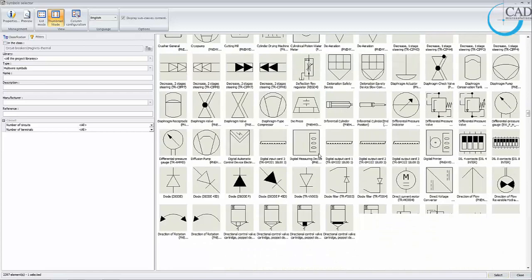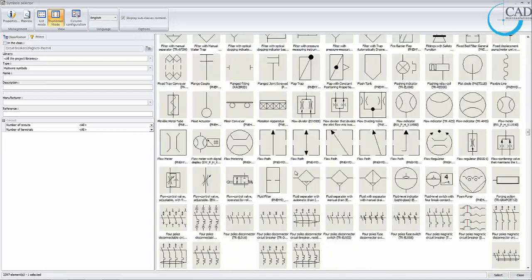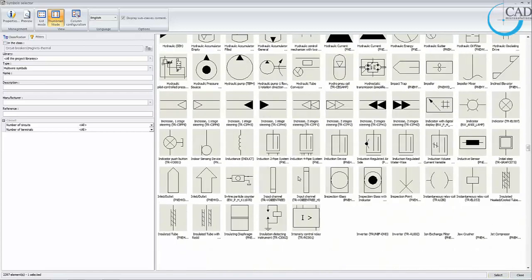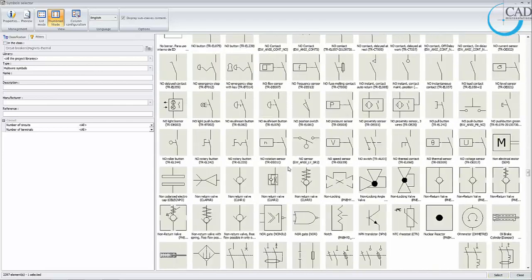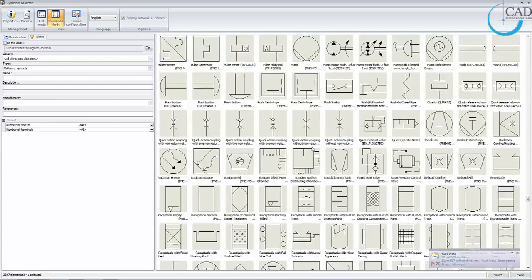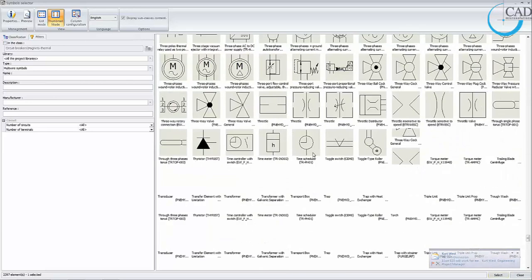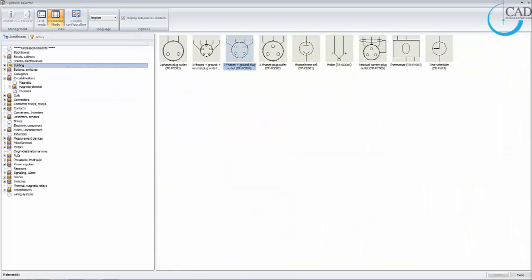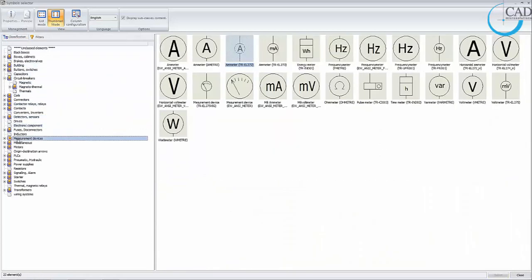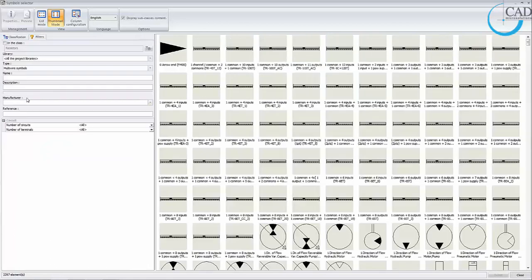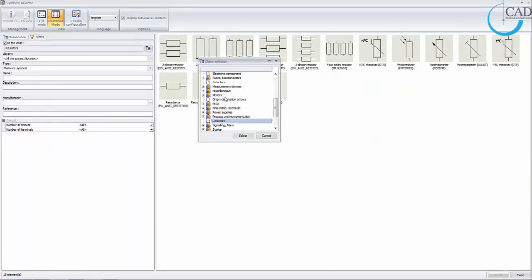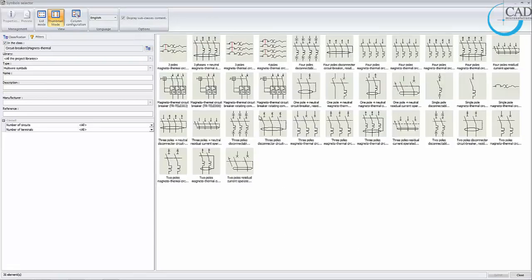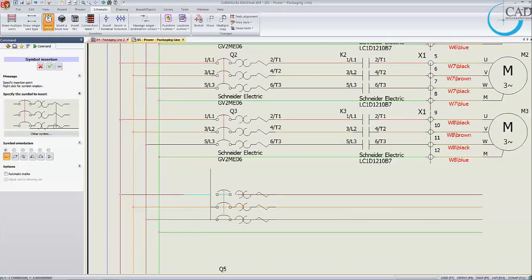The library includes relay coils, normally open contacts, connectors, circuit breaker symbols, switches, and more. You can use classification to filter through these symbols easily, or use a filter as well. We would like to add a thermal circuit breaker — a triple-pole one. We will associate this to the circuit breaker already in the line diagram drawing. It will tell you the symbol will be associated to component Q4. The manufacturer parts and circuits are populated right away based on what was initialized in the line diagram drawing.